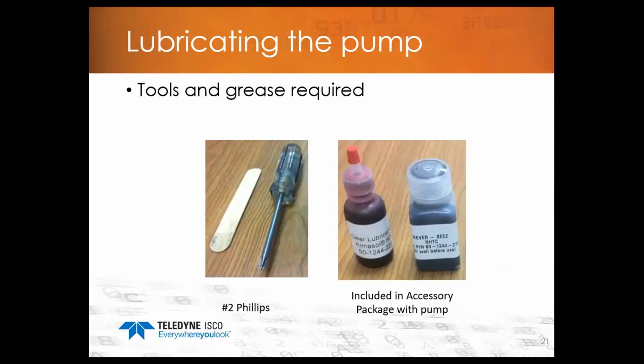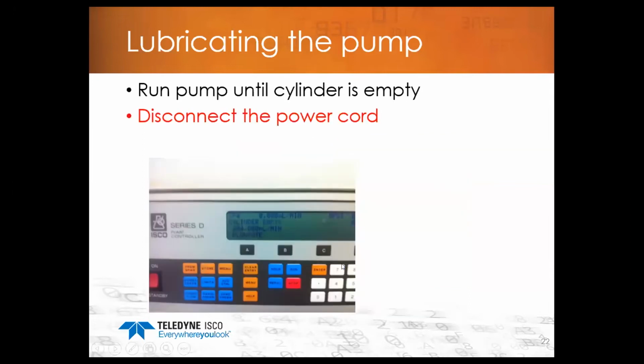The lubrication kit has two lubricants. We have an aerosol lubricant. It's kind of a red colored lubricant. It almost has the consistency of syrup. That's the lubricant that you'll use on the soak pad in the bottom of the pump. The black lubricant, the Never-Seez, is what you'll use on the ball screw. Once again, since you're changing the seal, you already have the pump empty, so that'll be taken care of.